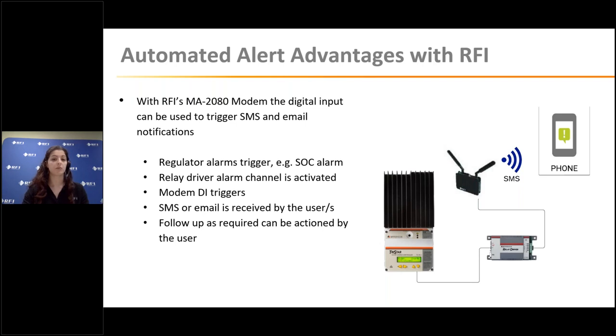It can be used to trigger both SMS and email notifications off of the IO, so it's really simple to integrate into the system. You connect that up on the relay channels from the relay driver into the IO, using a really simple twisted pair. They're all screw terminal Phoenix connectors, so easy to connect up in the field or when testing back at the office. So whatever alarm or fault is detected by the TriStar or the regulator on site, that's then triggered into the relay driver.